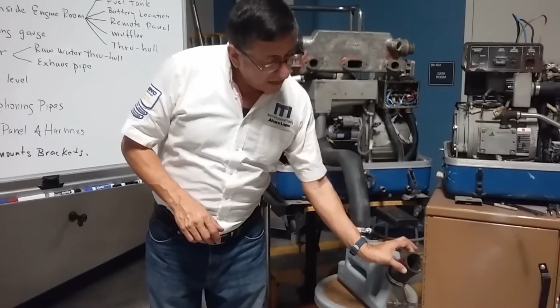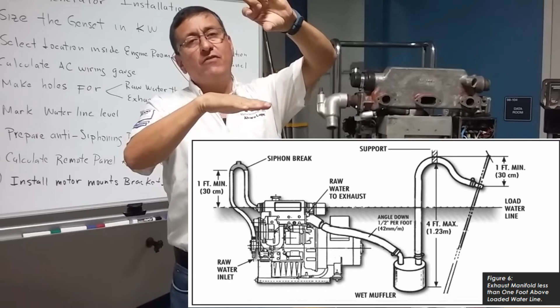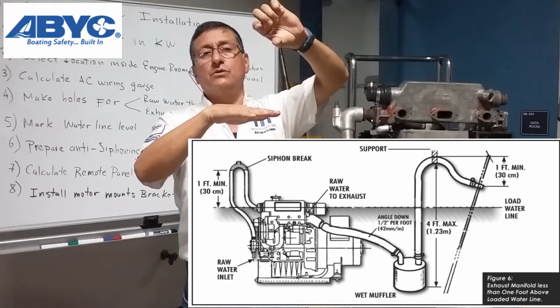Also be careful with the output line of the generator, the output pipe from the muffler. In some cases it has an anti-siphon, and the output at the end of the hose should be located 12 inches over the water line, minimum, per ABYC recommendation. The output line from the muffler has anti-siphon, and finally the output should be 12 inches over the water line. Another important recommendation is the through holes.